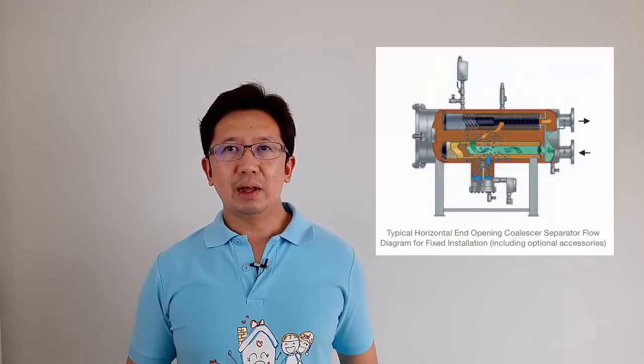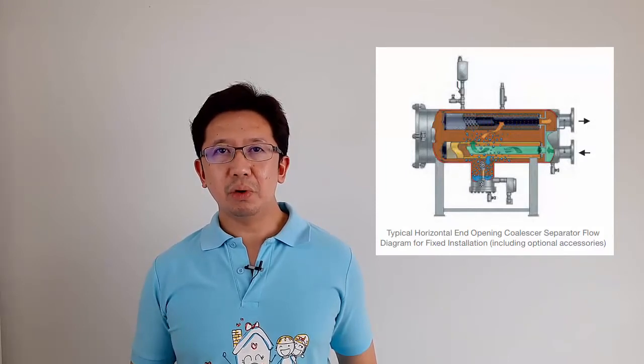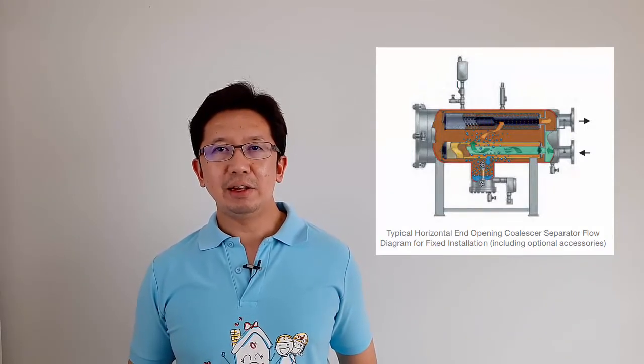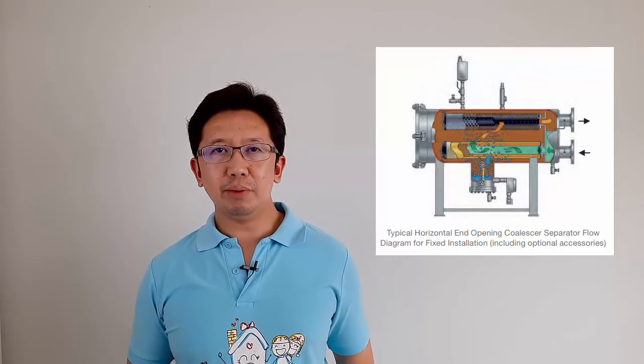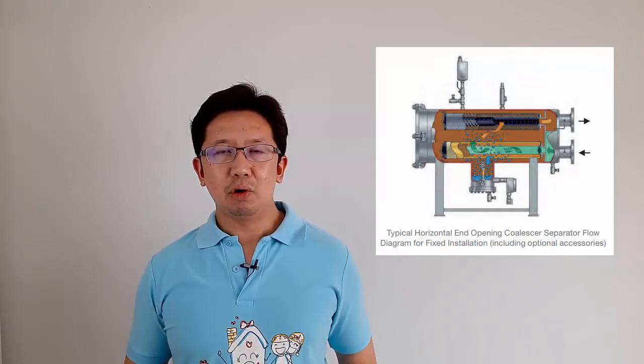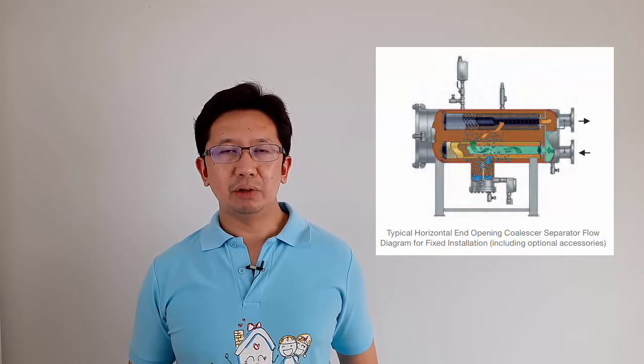Second one is rust. The pipeline from the storage tank, fuel truck and drum container tend to produce rust that can be carried in the fuels in small size particles. A high degree of filtration is required to remove the liquid water and rust particles from the fuels. This is the coalescer cartridge filter, which is used to coalesce the highly dispersed, such as emulsified, water particles into large water drops and filter out particle contaminants. Next one is dust and sand.